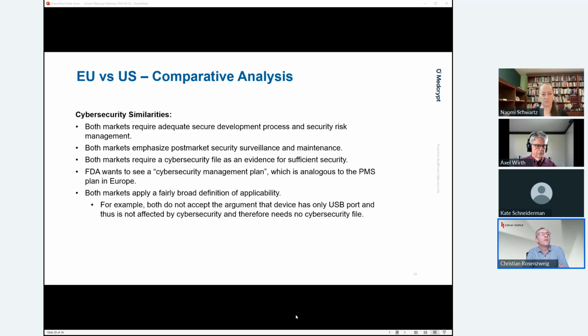Both markets emphasize post-market security surveillance and maintenance. Naomi said that already for the FDA. What are the expectations? We see that FDA requires a cybersecurity management plan. So that's more a product-related document that you have to provide. And the Europeans focus more on the quality management system, so they expect a description of post-market security activities within the quality management system. But I think that's a minor formal difference. Both markets apply a fairly broad definition of applicability. That is what we said before regarding the USB port.